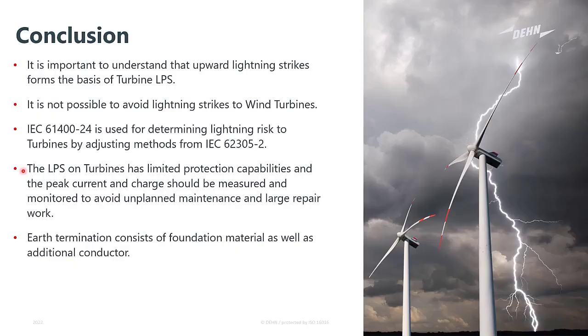And it's important to measure and monitor the lightning and charge current going through the wind turbine and the wind turbine blades and the lightning protection system and the receptors, so that those receptors are not overstressed and damaged catastrophically to the point where it damages big portions of the blade and causes fire and other catastrophic failures. It is also then important to consider the earth design, and to ensure that the earth design is safe against step and touch voltages by doing a safety earthing simulation using something like XGS Lab. But the earth termination system mainly consists of the foundation material, and you can add additional ring conductors if you are concerned with step and touch, or there's a requirement to drastically reduce the earthing resistance.